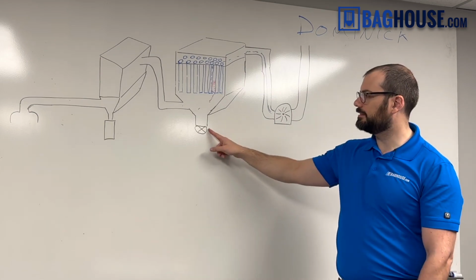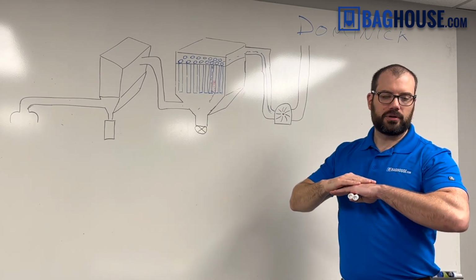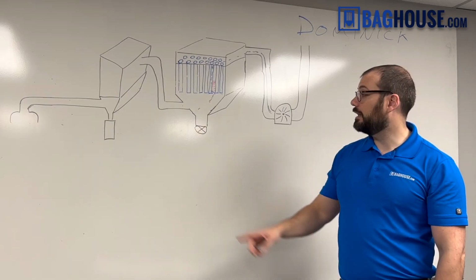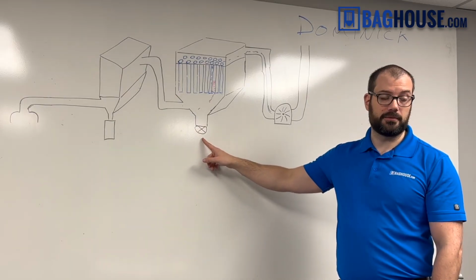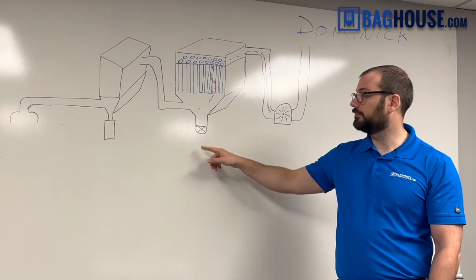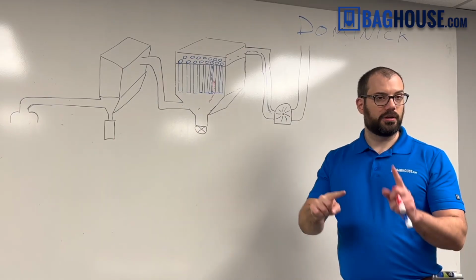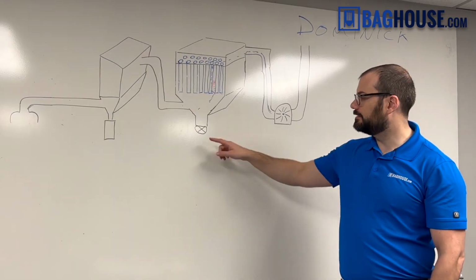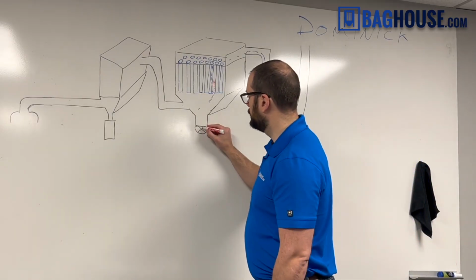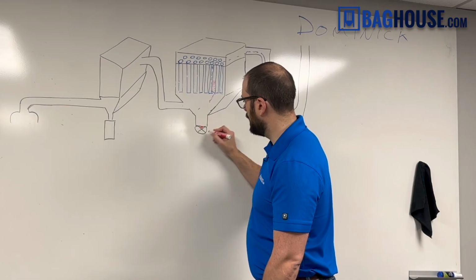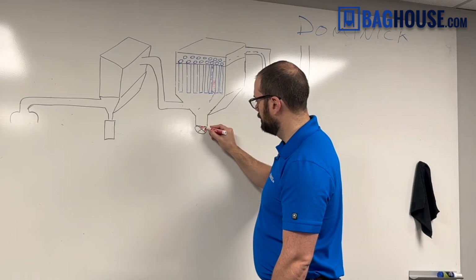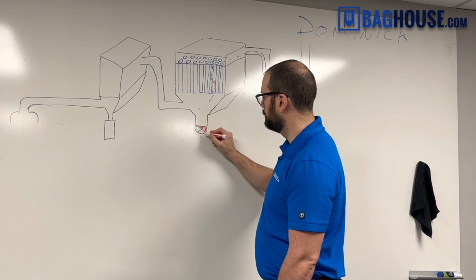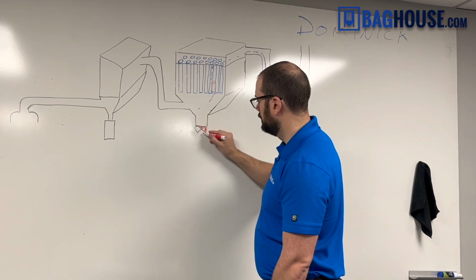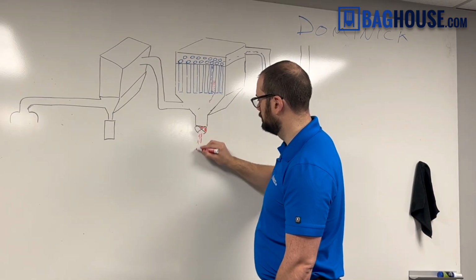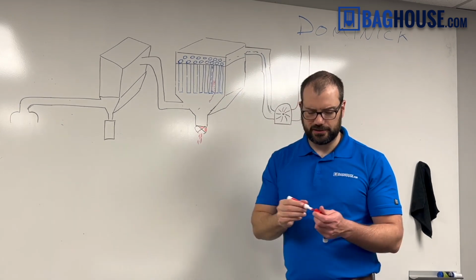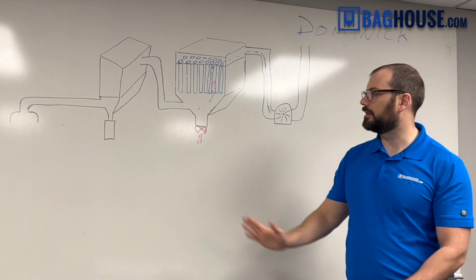So we have to have a device here that seals it but also lets dust flow out. That's why you have rotary airlocks on the bottom, your dust discharge valve. The rotary valve spins, and as it spins it fills with dust. Since there are multiple blades, as it turns around, the dust falls out, but the blades still touch the side, keeping the seal so air can't go up.